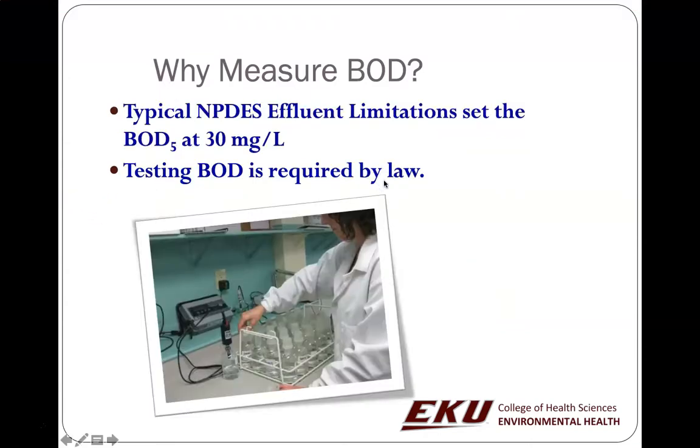All right, so typical NPDES permits allow, in many cases, up to 30 milligrams per liter. These obviously can vary by stream quality and other effluent sources, or other people emitting wastewater to the stream. And BOD, to my knowledge, is on almost every wastewater plant's permit. I can't think of any that do not have BOD on their permit. Even industrial wastewater plants have to worry about complying with BOD.